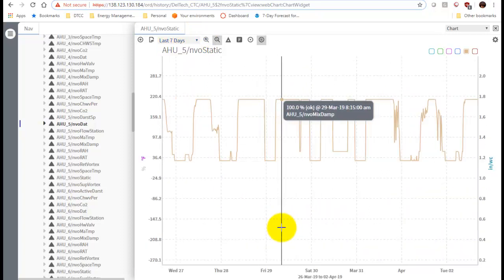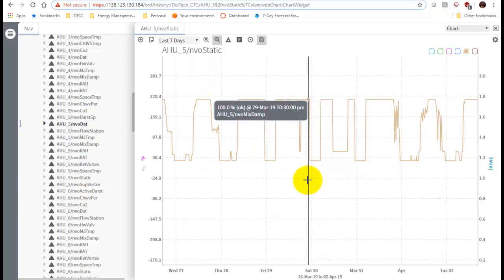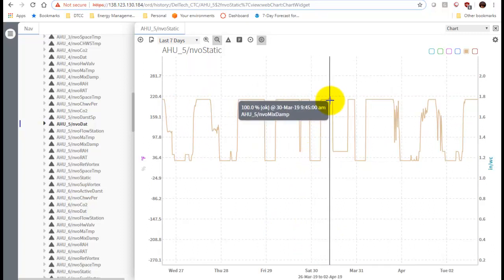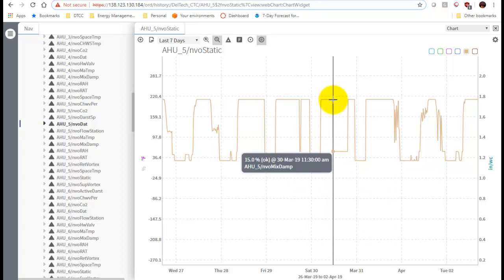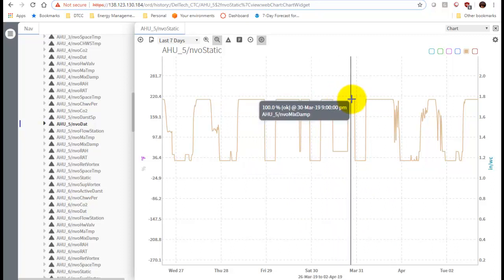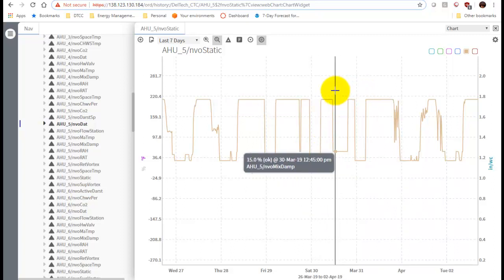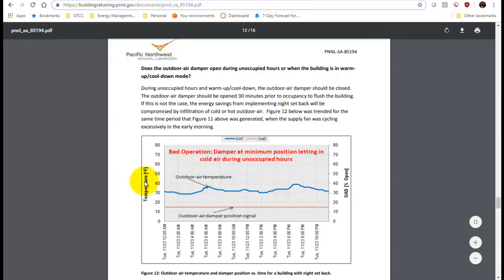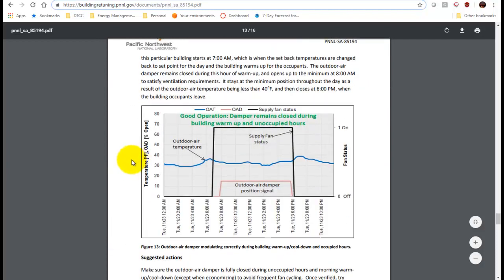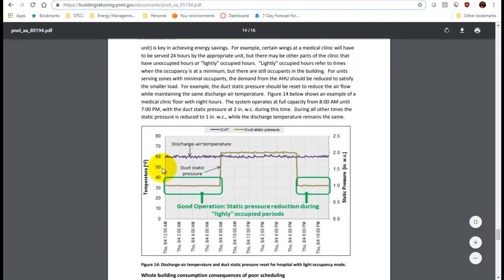Looking at the last seven days - here's Saturday, and it does go from around 6:15 and drops again around noon, which is good. But there's a problem on Sunday: the damper is open on Sundays, which it really shouldn't be. Those are the type of things you want to look for. Bad operation is when it's not going off on the weekends; good operation is when it remains completely closed during building warm-up and unoccupied hours.